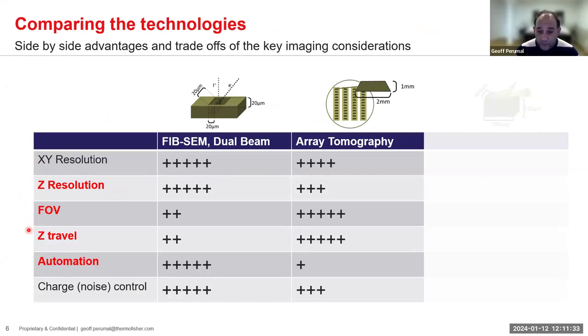X/Y resolution for these tools will be comparable since the electron beams are about the same. But for Z resolution, the focused ion beam will always give the best result — you can ablate down to a couple of nanometers. Field of view is another decider: if you're looking at cells, FIB might be best, but if you want the feel for tissues in a larger context, array tomography — limited by your diamond knife, which can be up to a few millimeters — may be the better approach.